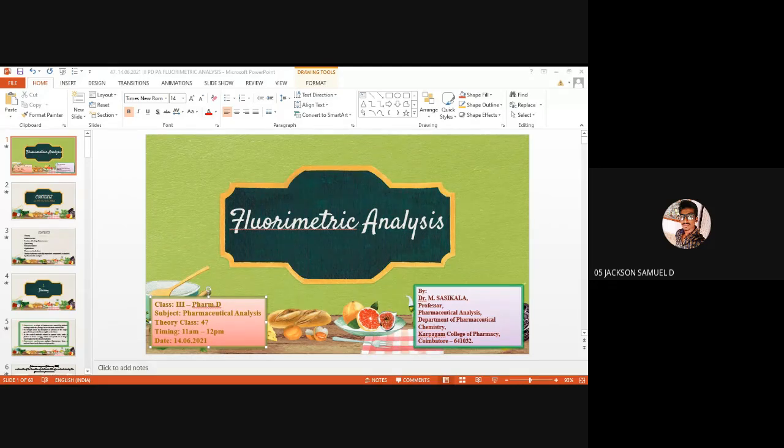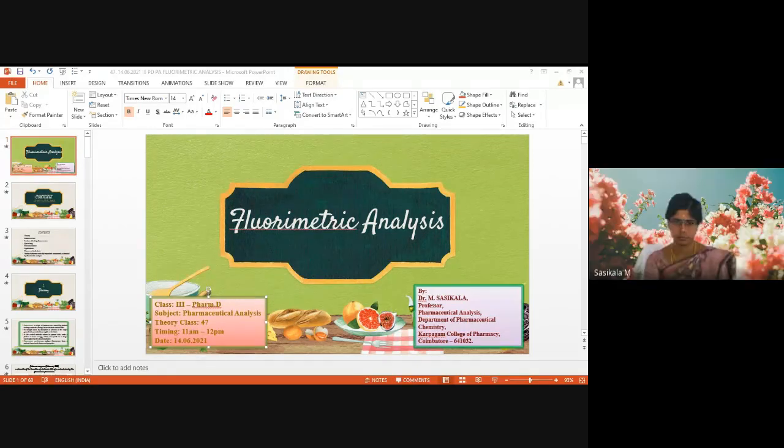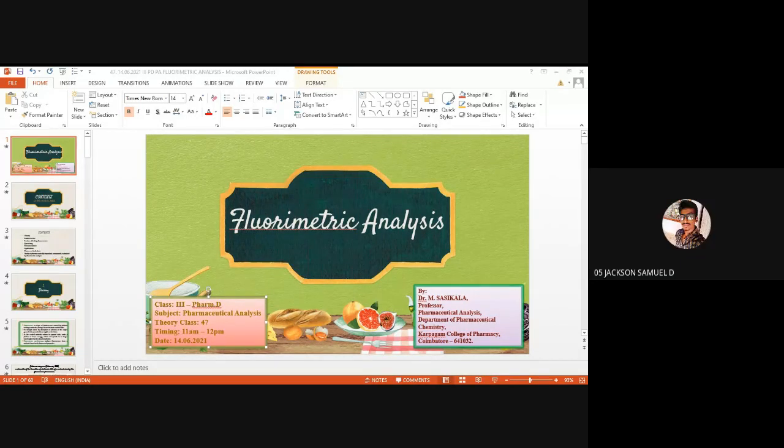Then light scattering: solid particles scatter the beam of light, so the result is a higher experimental absorption value than the real value. In chemical interference, the chemical being analyzed is contained within a compound in the analyte that is not atomized, so the result will be a lower experimental absorption value than the real value.